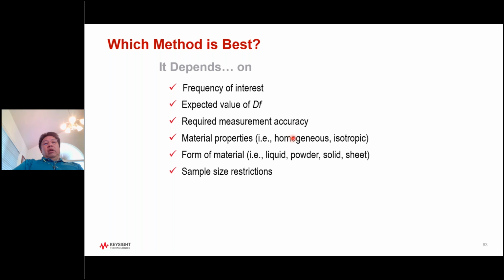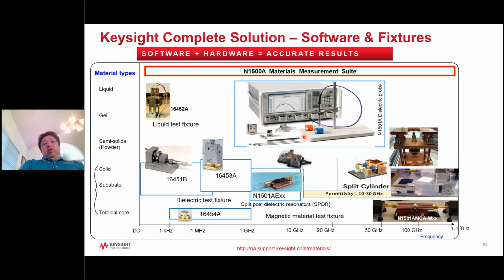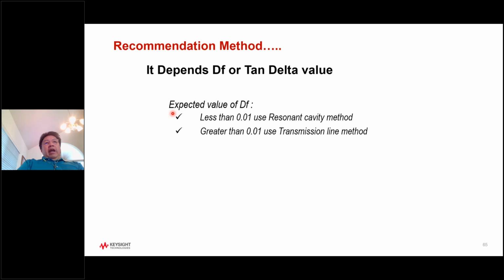When signal propagates through your material, there is X and Y plane propagation. So only certain limited measurement methods can measure both X and Y and give you the same answer. I'll tell you that later. So before you choose, I refer back to this table or slide that gives you an idea of how you can make your decision. So the answer to which method to use all depends on the critical parameter, which is your DF, or your tan delta value, or your imaginary part.